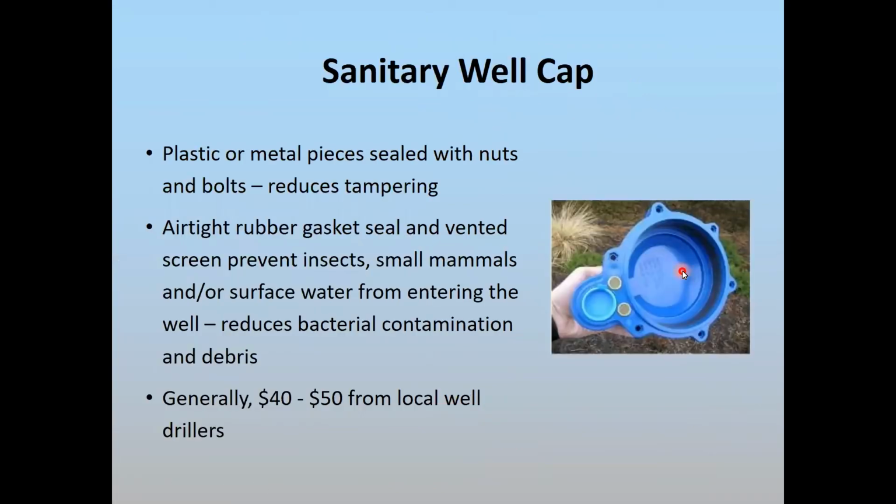Here's a plastic well cap that can be bought at most plumbing supply places. It has a rubber seal that goes around the well casing to seal it. This is access for the electrical conduit for the submersible pump, and it has these screened vents, and that'll prevent insects from getting into the well and actually adding bacterial contamination. And inexpensive, and does a lot in protecting your well from any sort of surface contamination or insects, things like that.